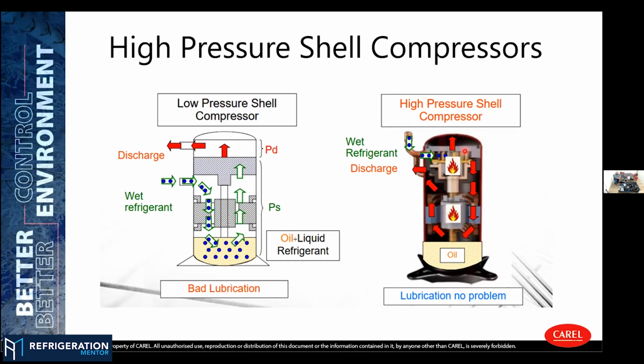Here, since this shell is pressurized at discharge pressure, and here we have our compressor chamber at least at suction pressure at the beginning, just by pressure differential, we can make the oil move from the bottom of the compressor to the compressor chamber. This allows us to run the compressor even at low speed without having problems with lubrication, because the oil will always move just by pressure differential. So this is one of the key points for this kind of compressor.